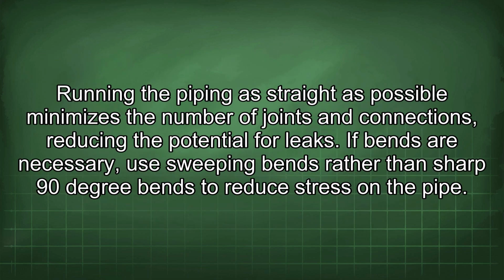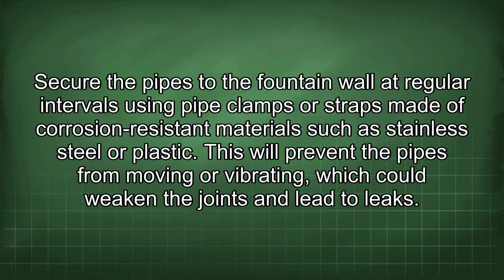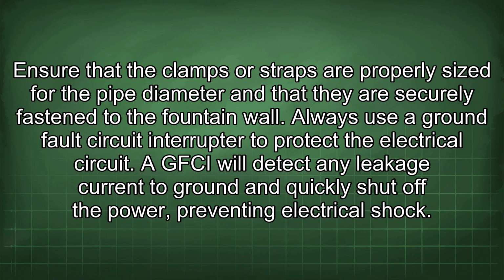Running the piping as straight as possible minimizes the number of joints and connections, reducing the potential for leaks. If bends are necessary, use sweeping bends rather than sharp 90-degree bends to reduce stress on the pipe. Secure the pipes to the fountain wall at regular intervals using pipe clamps or straps made of corrosion-resistant materials such as stainless steel or plastic. This will prevent the pipes from moving or vibrating, which could weaken the joints and lead to leaks.